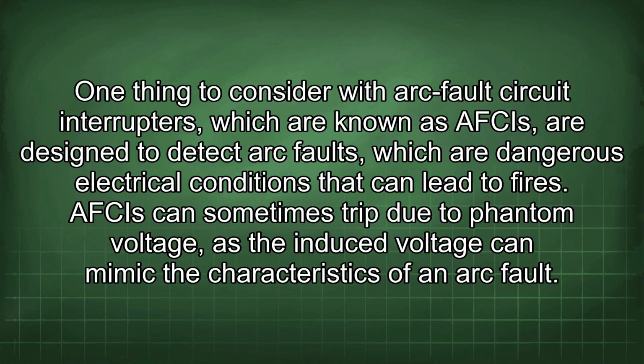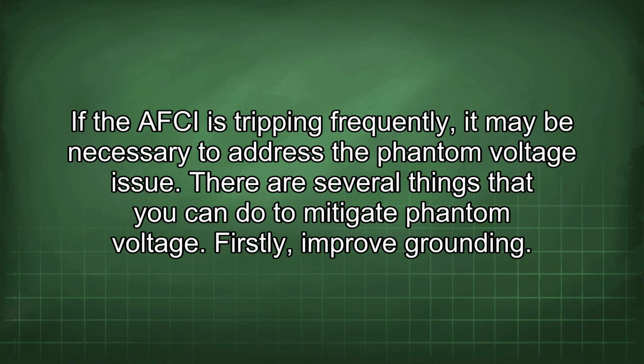One thing to consider with arc fault circuit interrupters, known as AFCIs, is that they are designed to detect arc faults, which are dangerous electrical conditions that can lead to fires. An AFCI can sometimes trip due to phantom voltage, as the induced voltage can mimic the characteristics of an arc fault. If the AFCI is tripping frequently, it may be necessary to address the phantom voltage issue.